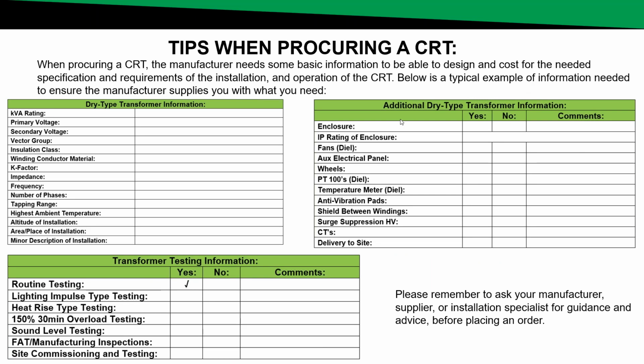When you are procuring a cast resin transformer, it is very important to supply your manufacturer with some basic information. This will allow the manufacturer to actually design the transformer specific to your requirements. You can see on screen, there's a typical example. kVA rating, primary voltage, secondary voltage, vector group, insulation class, winding conductor material, do you want aluminium or copper? K factor, is there some harmonics that need to be factored in? Frequency, number of phases, tapping range, so you can order your transformer with various tapping ranges.